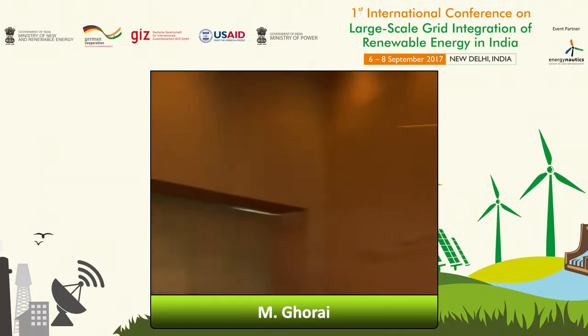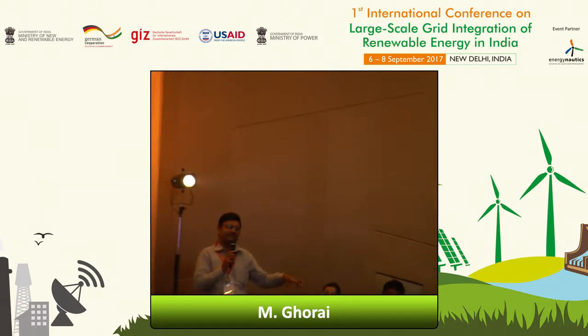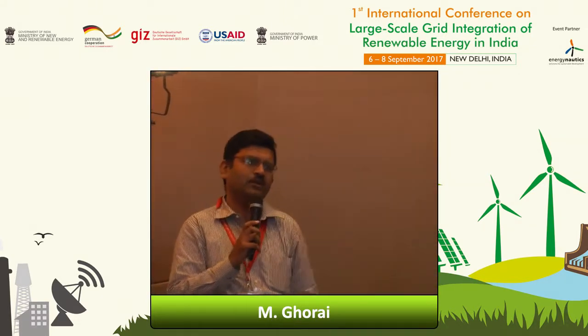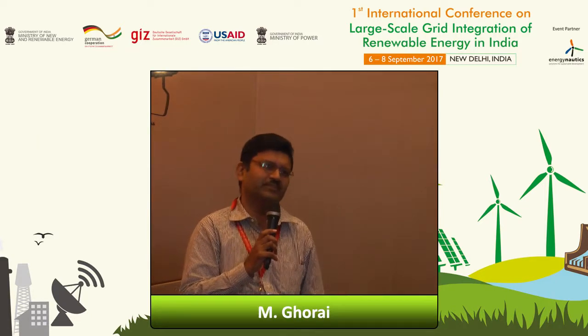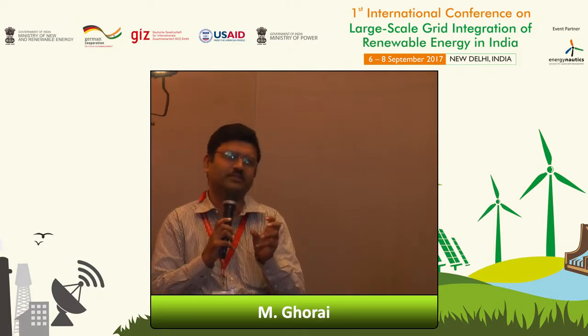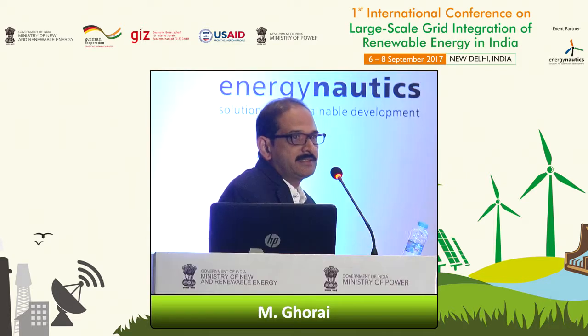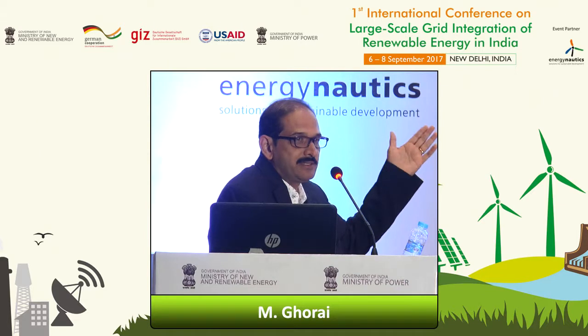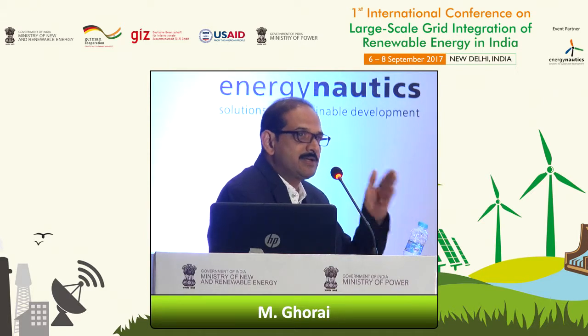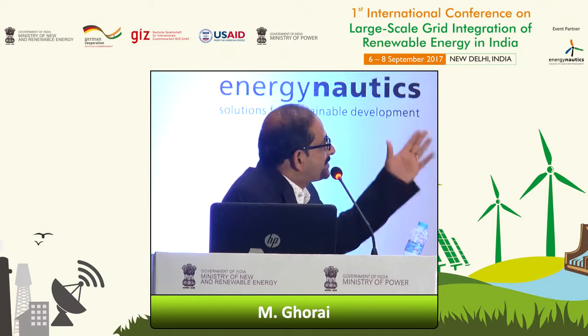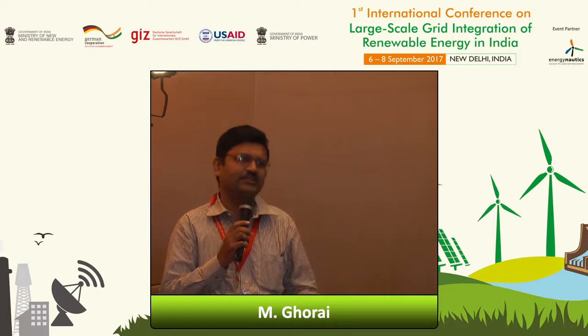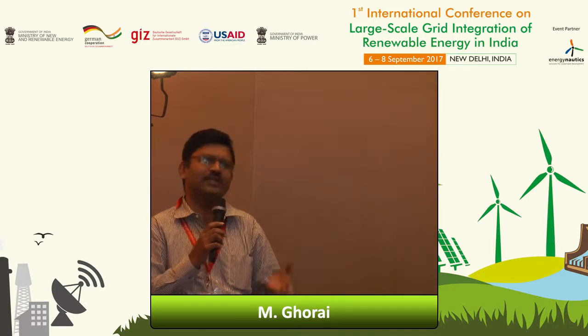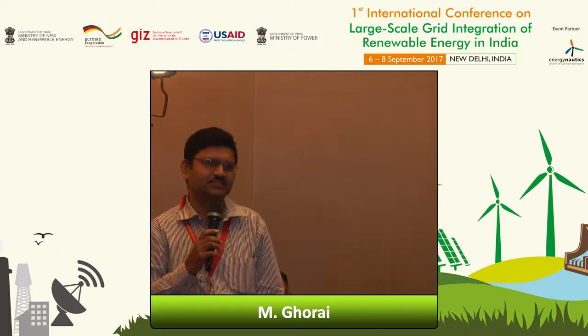Yeah, but this is concentrated. This is at a single place. So if something goes wrong, the whole thing goes wrong. Whereas if you have a capacity addition in each wind turbine, then one may go wrong, but still overall there is a support still available. Giving one concentrated STATCOM still has this disadvantage. I said that's the cost economics of the wind turbines. Wind turbines become very, very expensive, and then probably it becomes difficult again. And what you are doing is you are multiplying, say for example, there are 100 turbines or 50 turbines, you are multiplying that additional cost by 50 times, whereas here it's one or two. It's not much. I mean, ultimately you are supplying the same var. So ultimately, given the same voltage level, you will have to add the same current capacity. So that way economics should not be difficult.